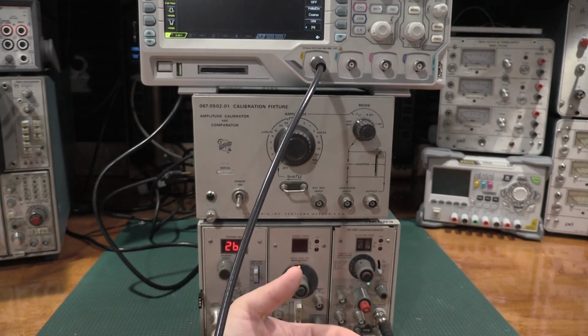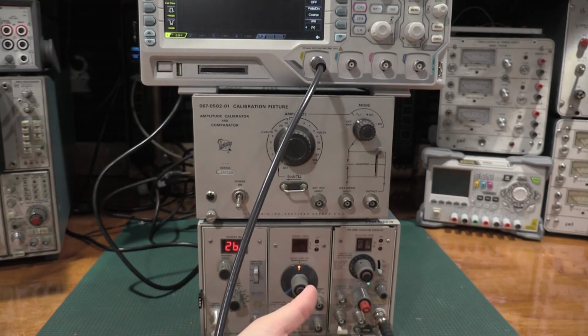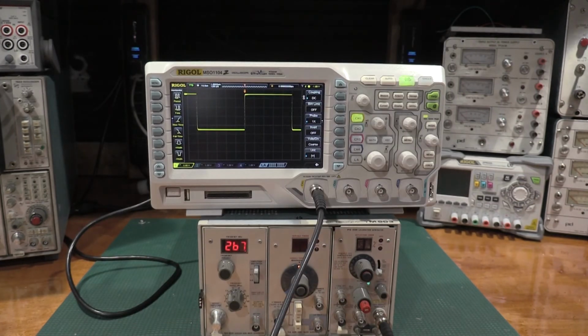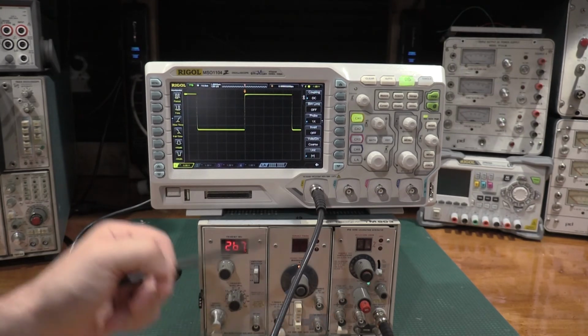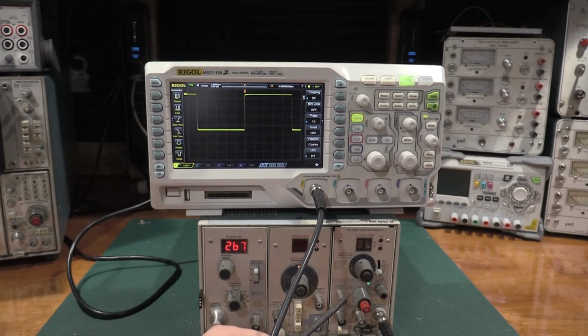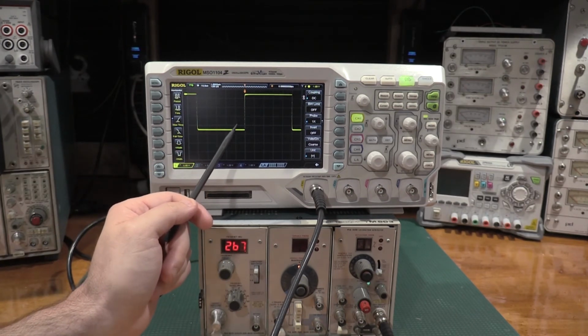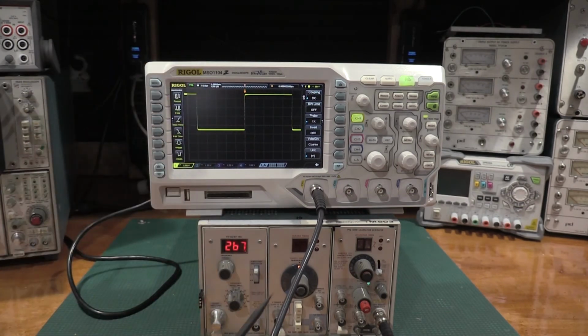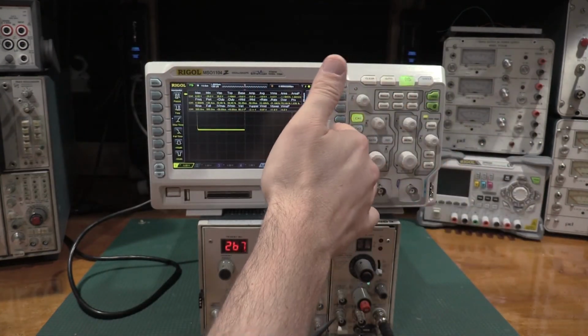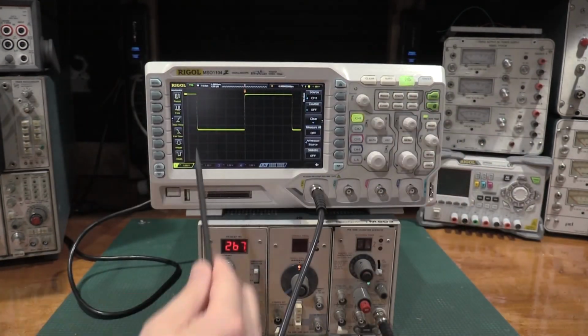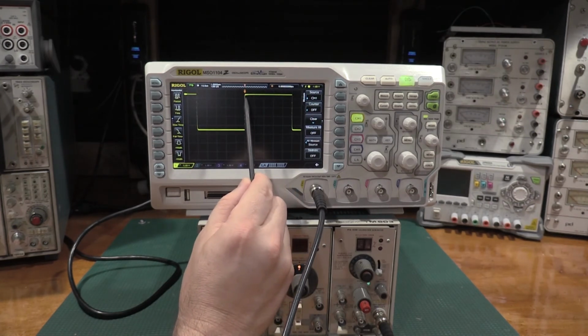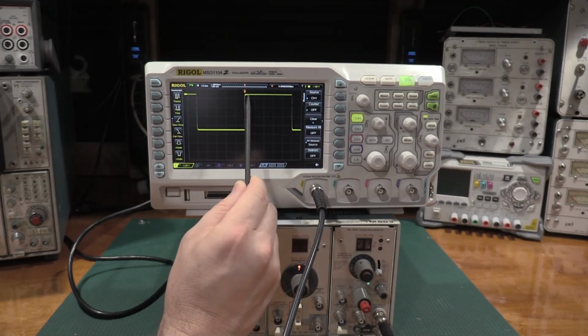Now, for most of the low frequency tuning and things like that, you do it with a square wave. So a lot of the tuning that gets done, we do it with a square wave. So gain set by the calibrated steps. I find that to be very important, very valuable. The other thing that's very valuable is this is a moderately fast edge, not really. 300 nanoseconds, moderately fast. But it's a fast rise with a nice clean top. There's no ringing. There's no nothing.